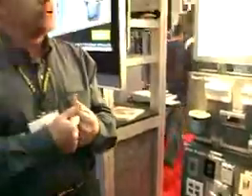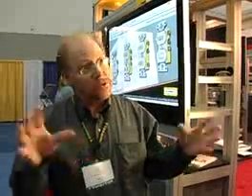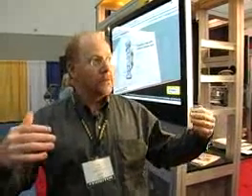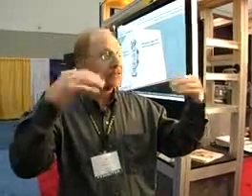Is there anything else you can show us right now? One of the other issues that came up was under cabinet and under counter power. How do you get a receptacle under the cabinet? And the question is why? Well, there is a lot of design work that's being done with granite backsplashes these days or tile work. And because of the code requirement, you need to put a receptacle every 4 feet. It really doesn't look that great if I've got some nice design work. So once again, we went out in the marketplace and customers said, can we put it high underneath the cabinet? And the answer is yes, we can.